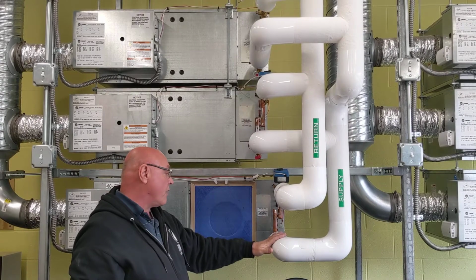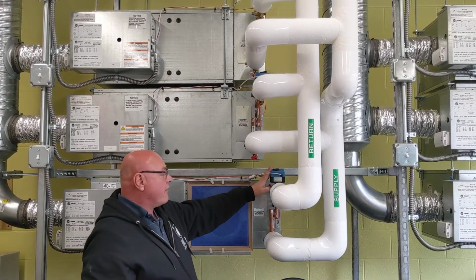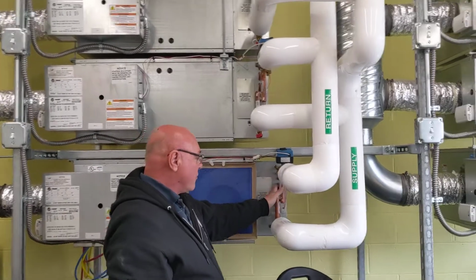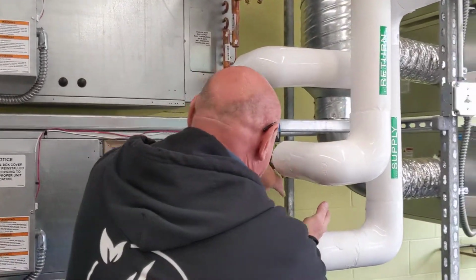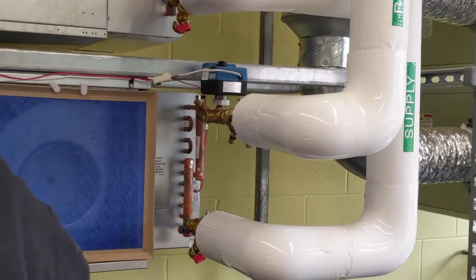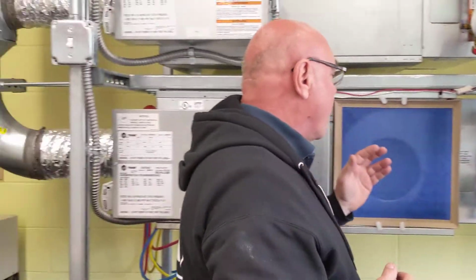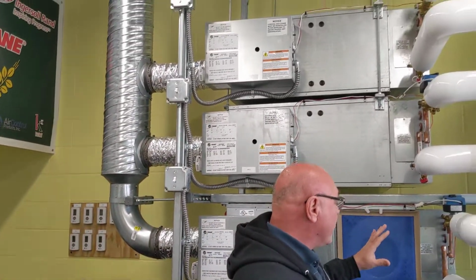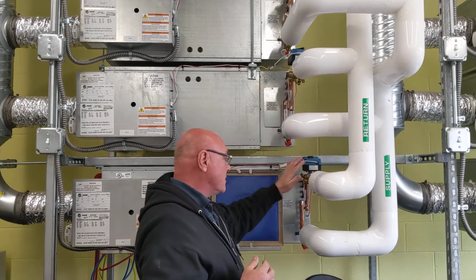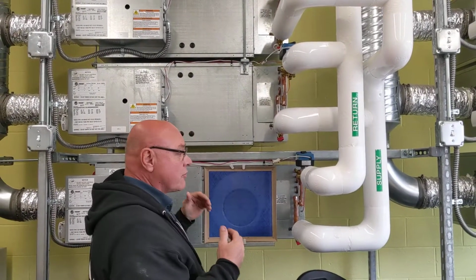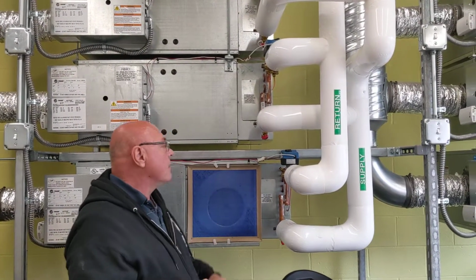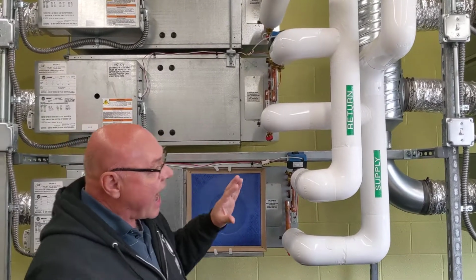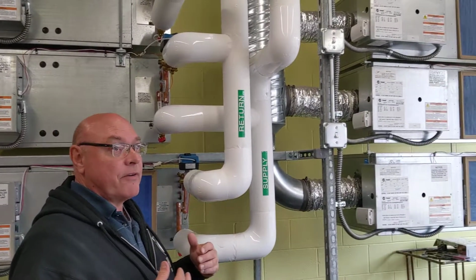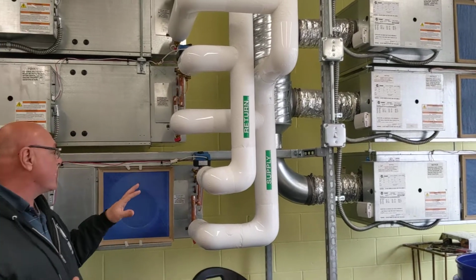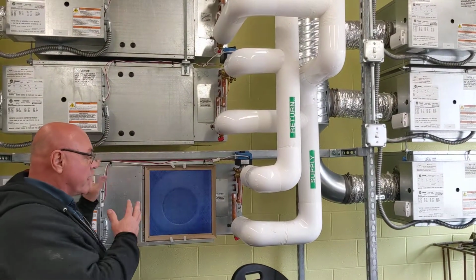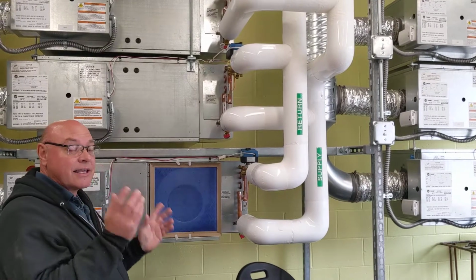We have water in it and water out. If this valve opens up, we're sending heat through here, and that fan turns on, and it brings heat across and out into the room. If we don't need any heat, the valve closes, and we just have our air coming through the ductwork. So that's basically how these work, simplified, and we'll get much further into VAV boxes when we cover the whole VAV box, but this is how the heating loop works.